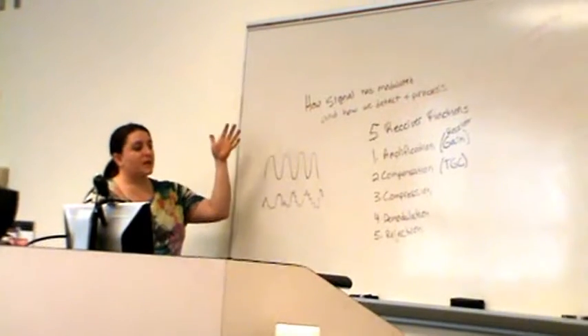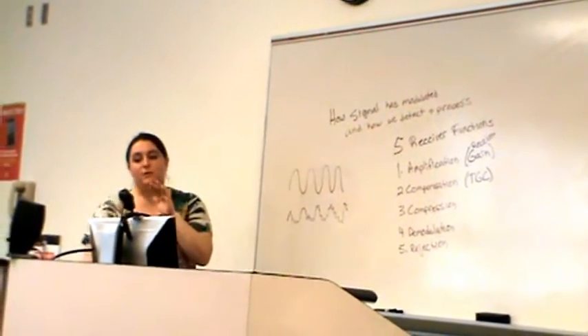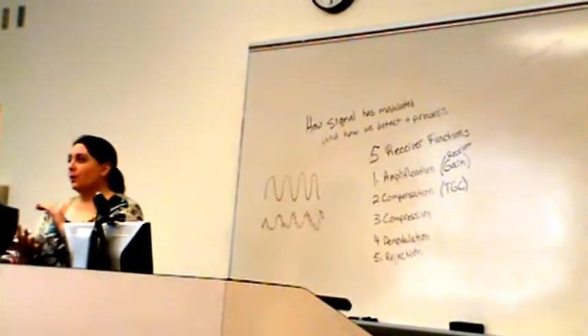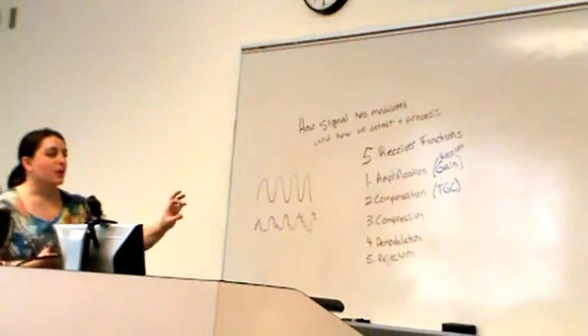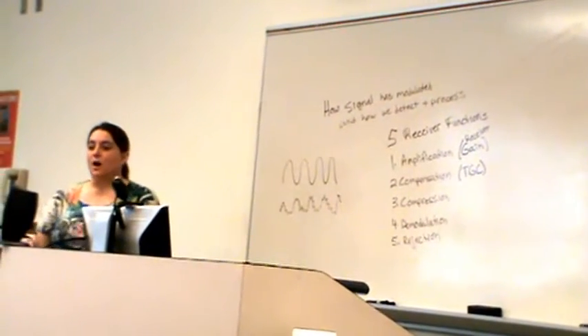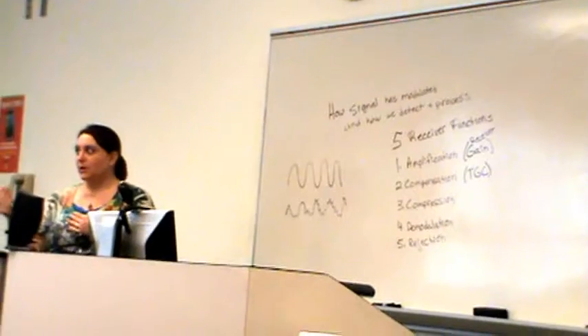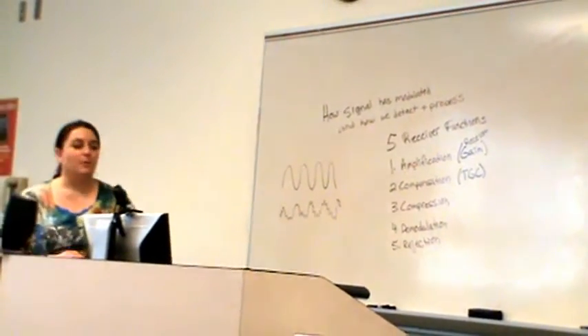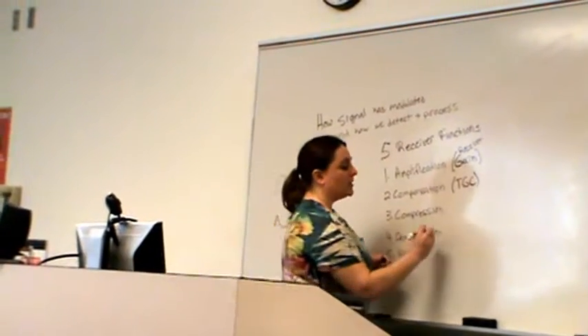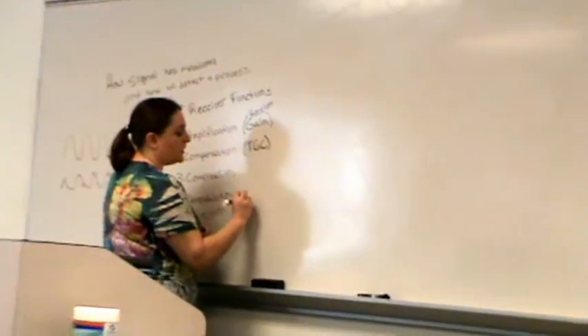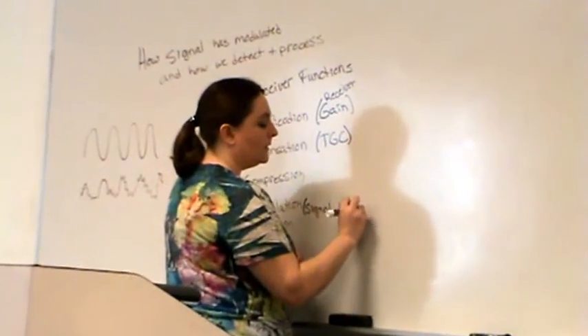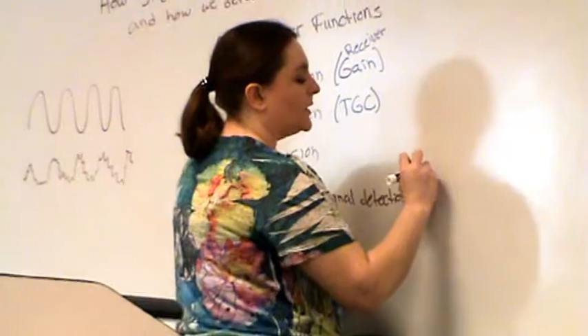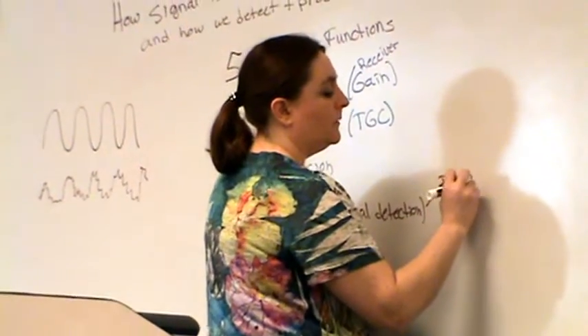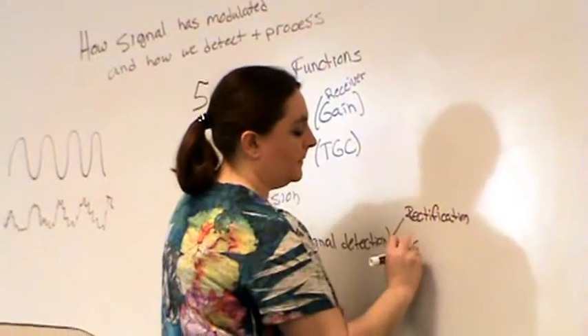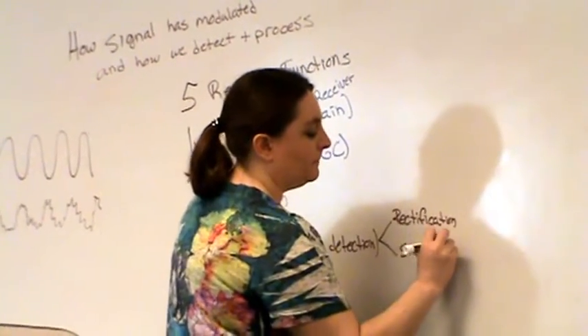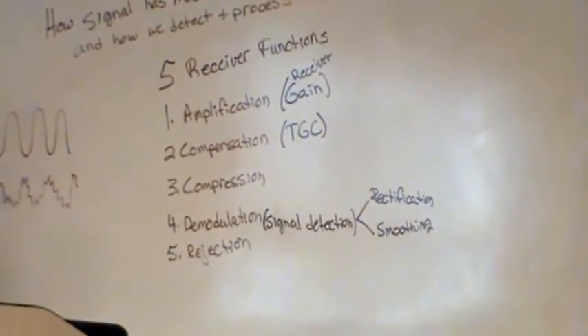Then we do compression. Remember that the dynamic range that we have in these signals is so huge that we have to do some compression in order to make it usable by the rest of the system. And again, most of this compression is done in the system itself. We do have a compression knob. The compression knob we have is more display compression, not necessarily compression here, but we do have a compression. And then demodulation, this is the one that's the signal detection thing. And remember, demodulation is 2 steps. Rectification, smoothing or envelope detection.